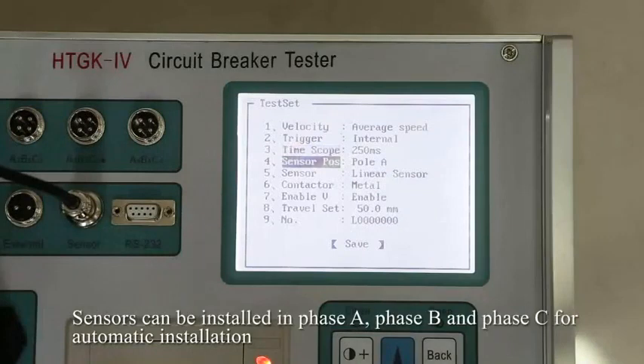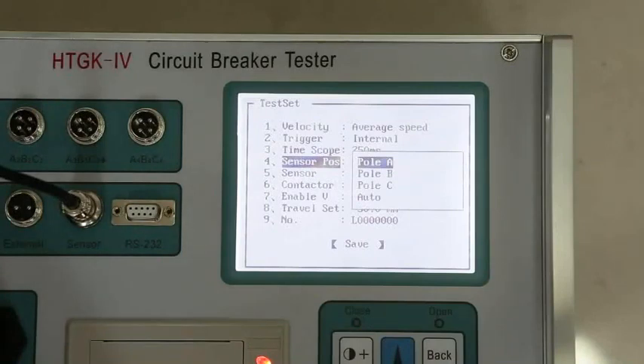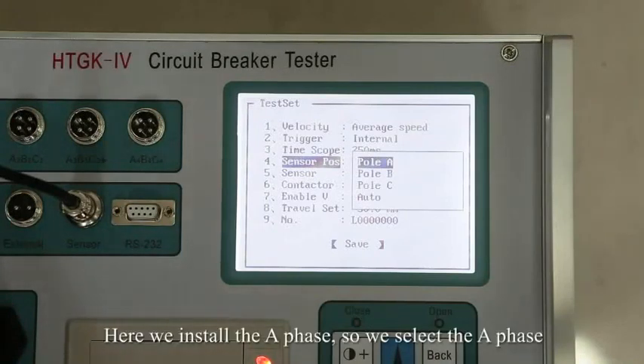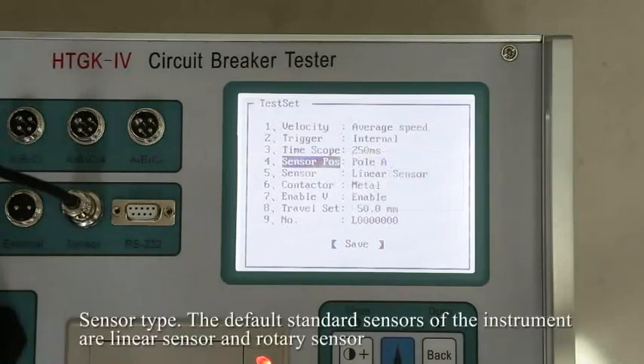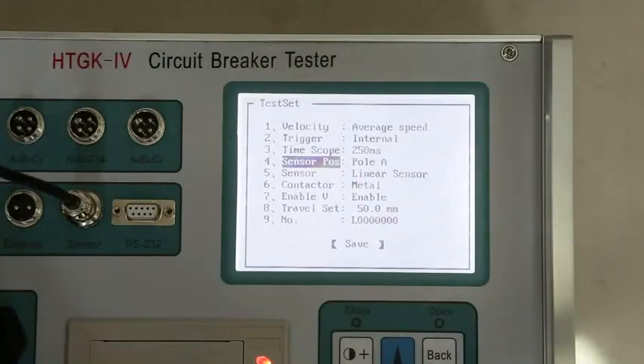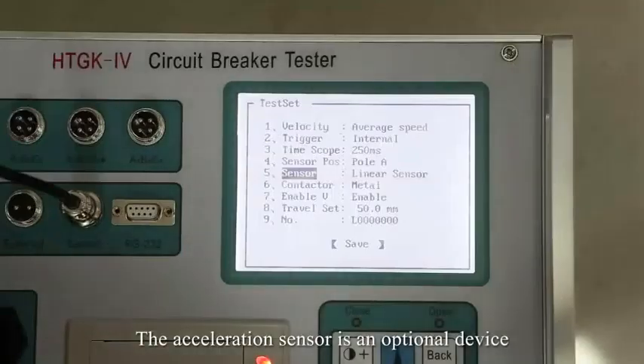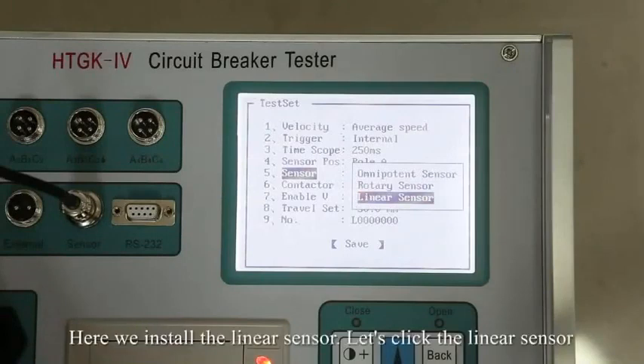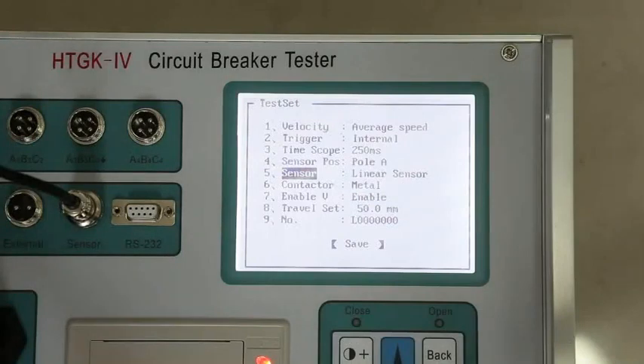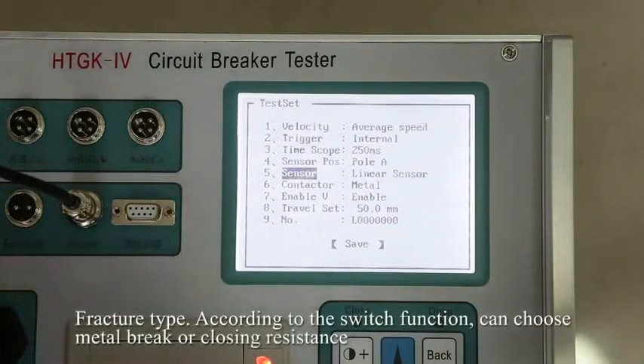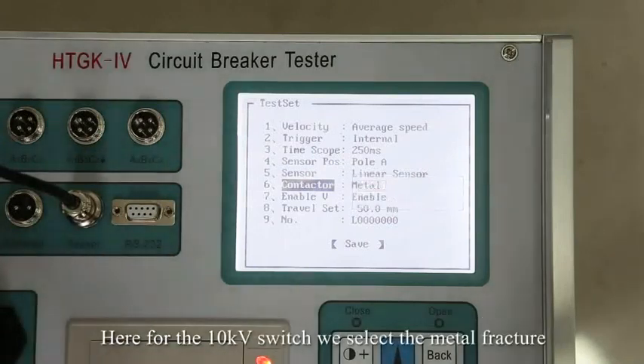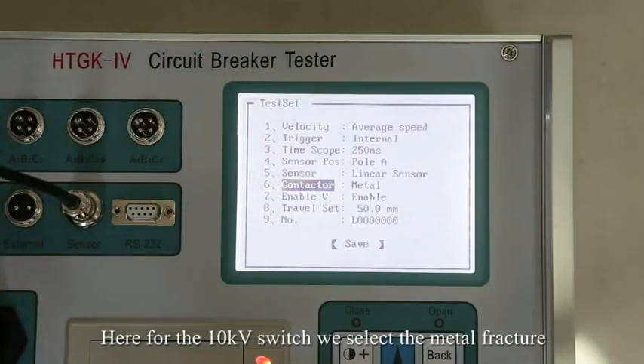Sensors can be installed in phase A, phase B, and phase C. Here we install the A phase, so we select the A phase. Sensor type: the default standard sensors of the instrument are the linear sensor and the rotary sensor. The acceleration sensor is an optional device. Here we install the linear sensor, so we click linear sensor. Fracture type: according to the switch function, we can choose metal break or closing resistance. Here for the 10 kV switch, we select the metal fracture.